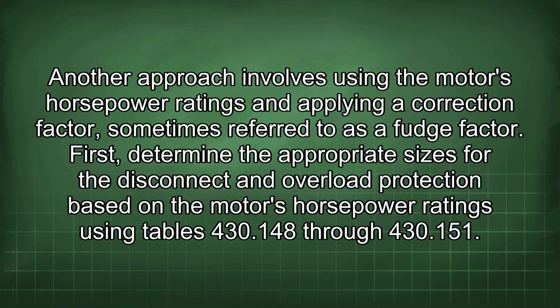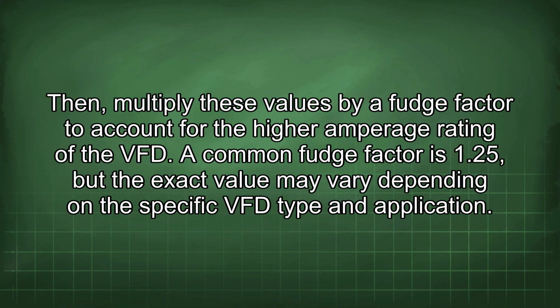Another approach involves using the motor's horsepower ratings and applying a correction factor, sometimes referred to as a fudge factor. First, determine the appropriate sizes for the disconnect and overload protection based on the motor's horsepower ratings using tables 430.148 through 430.151. Then, multiply these values by a fudge factor to account for the higher amperage rating of the VFD. A common fudge factor is 1.25, but the exact value may vary depending on the specific VFD type and application.